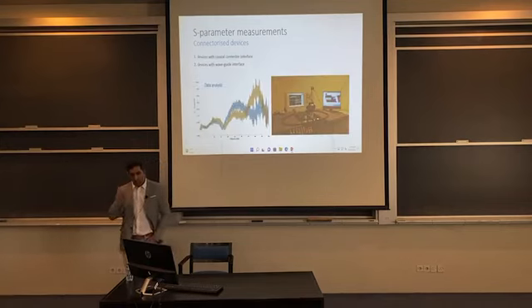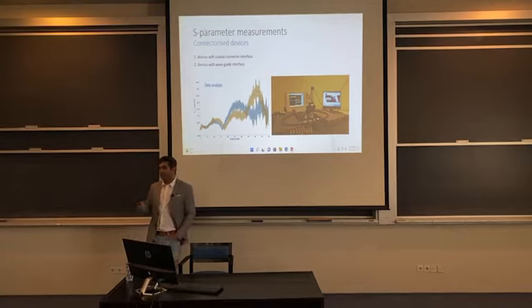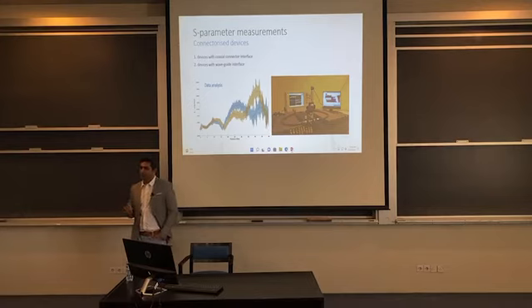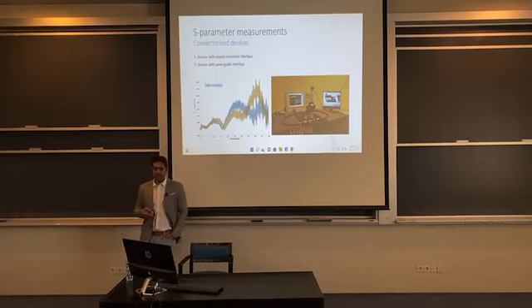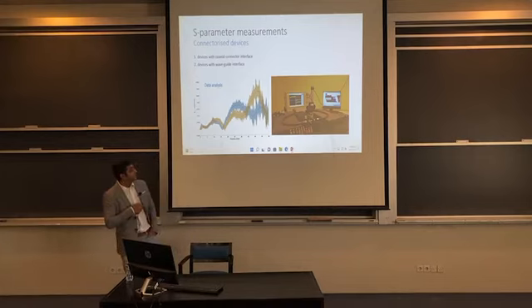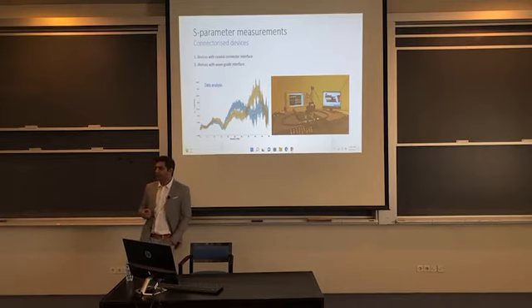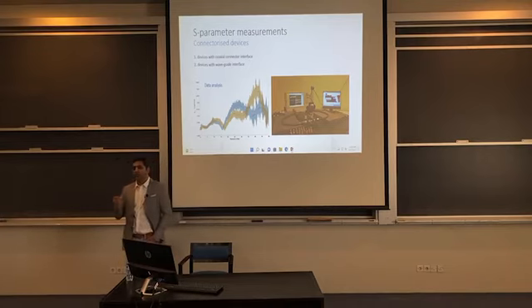Going from a simple measurement to something meaningful requires accuracy estimation, because a measurement without that doesn't mean much. A measurement gets a value, and with that value you need to say something about the accuracy, which we call an uncertainty. A measurement with an uncertainty contribution is what we're looking for. At the end of the day, we need to develop a measurement capability that allows us to estimate an uncertainty for that particular measurement.